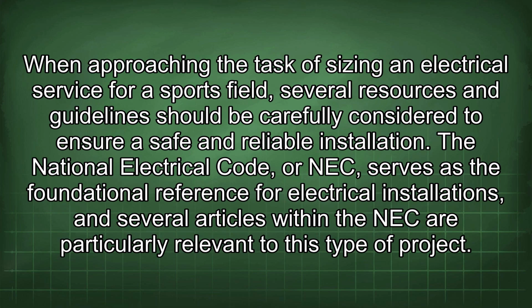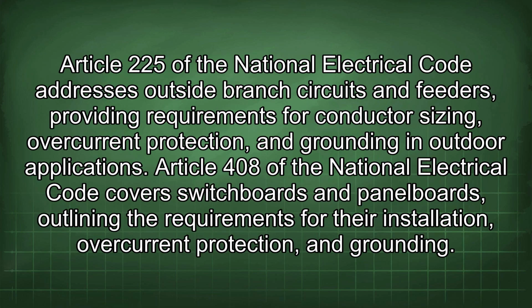When approaching the task of sizing an electrical service for a sports field, several resources and guidelines should be carefully considered to ensure a safe and reliable installation. The National Electrical Code, or NEC, serves as the foundational reference for electrical installations, and several articles within the NEC are particularly relevant to this type of project. Article 225 of the National Electrical Code addresses outside branch circuits and feeders, providing requirements for conductor sizing, overcurrent protection, and grounding in outdoor applications.